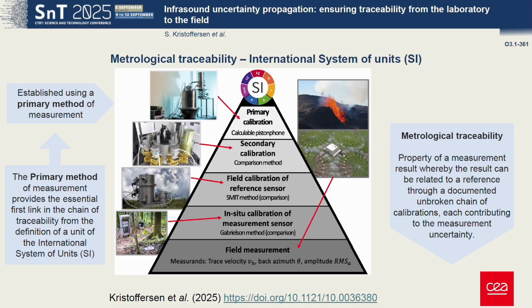The idea with metrological traceability is that we have these various levels: primary, secondary, field calibration, and finally in situ or on-site calibration of our sensors, which allow us to have a traceable calibration back to SI units, pascals in this case.